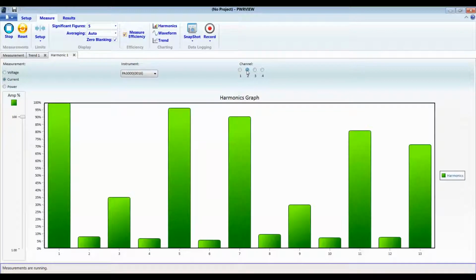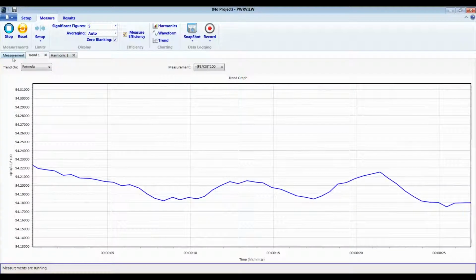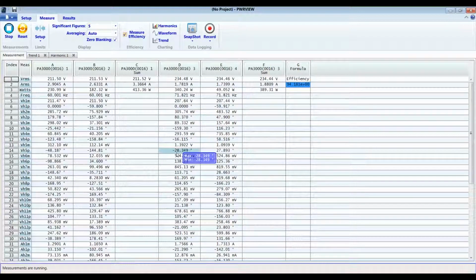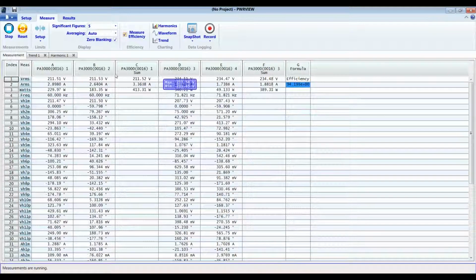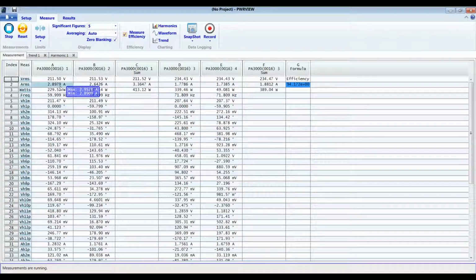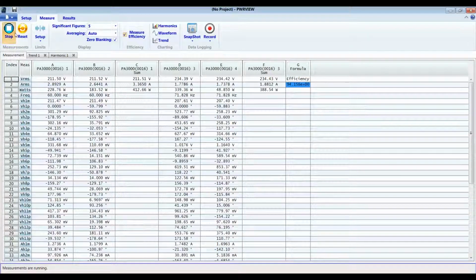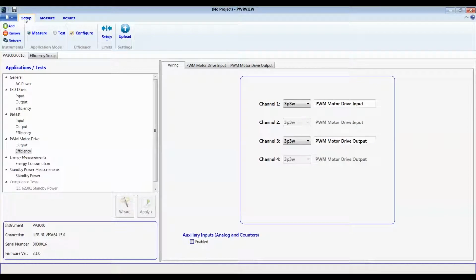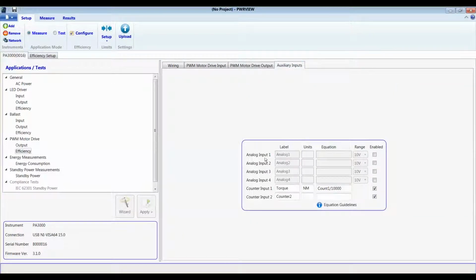Now, if you are interested in measuring torque, speed or thermal inputs simultaneously while you are measuring efficiency, we can use the auxiliary inputs on PA3000, right? So let's stop the measurements momentarily and go back to the setup page. Okay? So on the setup page here under wiring, there is an option to enable aux inputs. Okay? Aux inputs or auxiliary inputs can be used for measuring any external signal, either from a torque sensor, speed sensor, thermal sensor, or any other sensors that have voltage, analog or digital outputs.